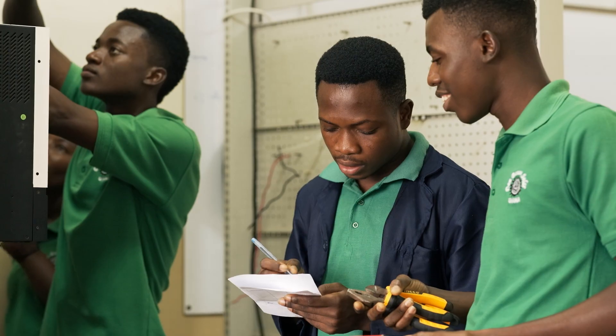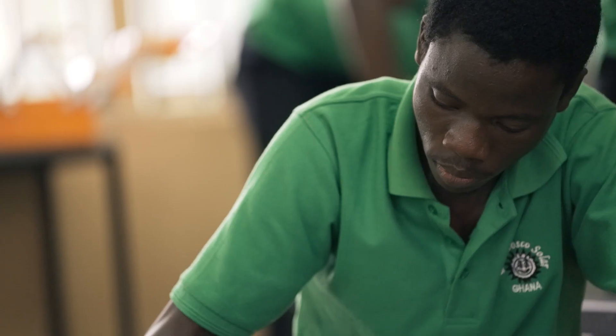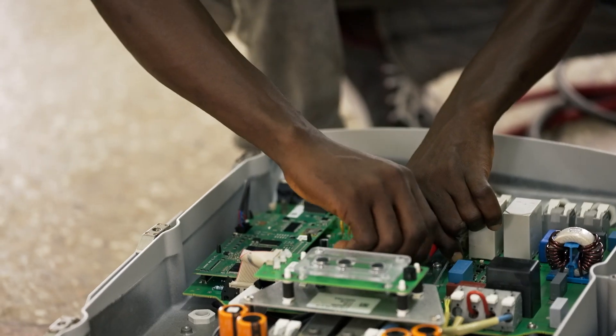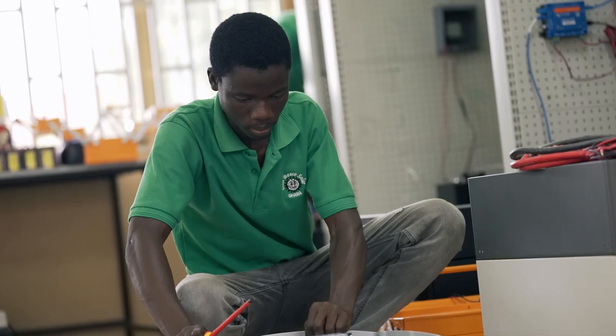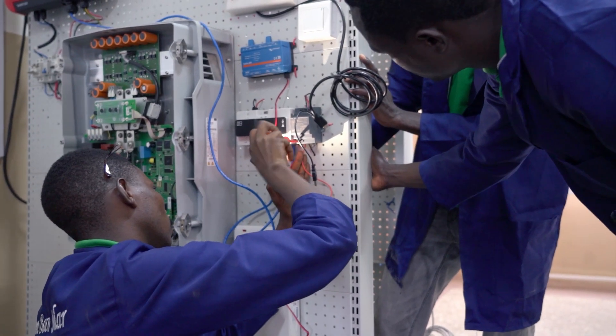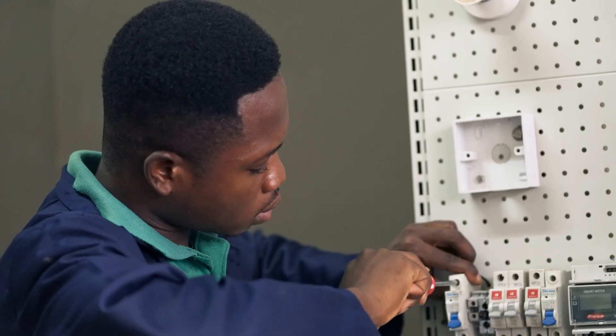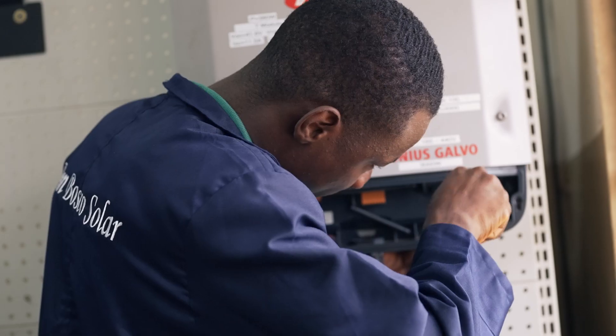As a result, high power consumers such as air conditioners, water heaters, and water pumps are programmed to only run depending on the outside temperature, time of day, or when there is enough PV power production and battery charge. With the help of smart load management, more than 96 percent self-sufficiency has been achieved and the mini grid has high redundancy.